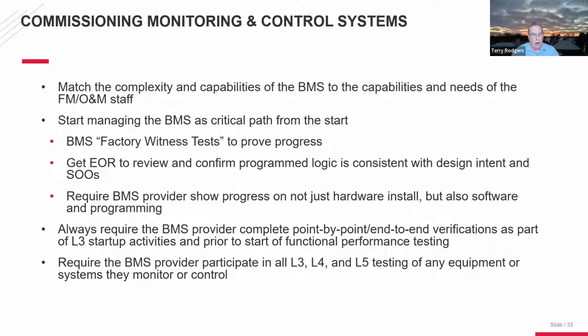Always require the BMS provider complete a point-by-point end-to-end verification as part of their level 3 startup activities. That should be included as part of the startup of a piece of equipment. So when the mechanical contractor goes out and starts up a new pump or an air handler, you need to make sure the BAS is included as part of that startup, where they're comparing field readings like a thermometer or pressure gauge against what's being read back at the BMS system. The communication, the vendor lookup tables, all that needs to be completed.